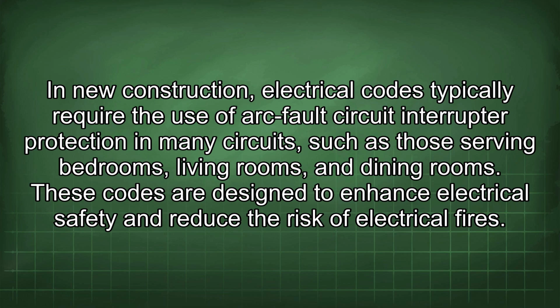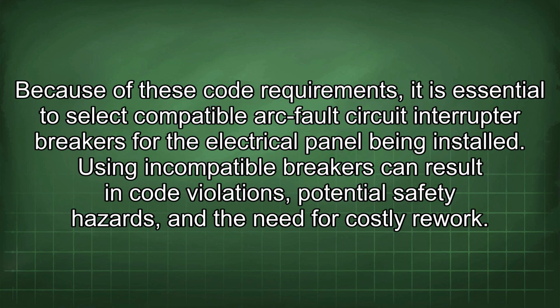In new construction, electrical codes typically require the use of arc fault circuit interrupter protection in many circuits, such as those serving bedrooms, living rooms, and dining rooms. These codes are designed to enhance electrical safety and reduce the risk of electrical fires. Because of these code requirements, it is essential to select compatible arc fault circuit interrupter breakers for the electrical panel being installed. Using incompatible breakers can result in code violations, potential safety hazards, and the need for costly rework.